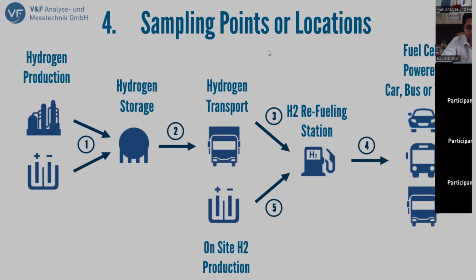So the instruments that are already in the field are usually used in a stationary environment where gas from these sites is then transported in a suitable gas cylinder to the instrument, which is then attached there, and the analysis then proceeds in a closed location, like a lab or a room or a container. But in principle, with the right gas treatment and the installation of piping and all of that, once these things are established, you can also provide the gas to the instrument from any of these sites.